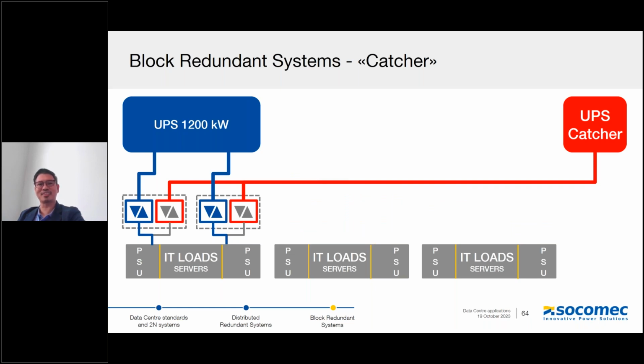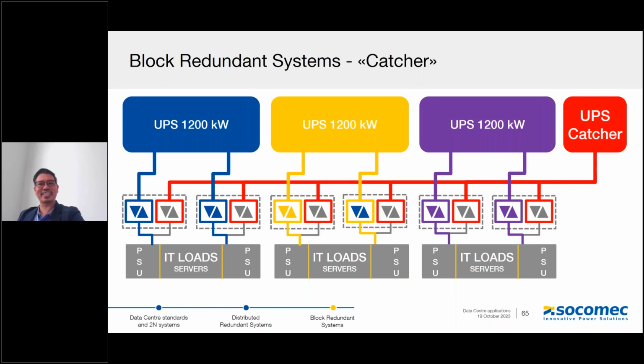You have your source B as your UPS catcher, but also your source A as your main UPS. However, the catcher won't be optimized if it is only a catcher of one system. So the catcher can be a catcher of multiple systems - that's where all your savings will go. You'll have less UPSs, meaning less UPS, less batteries as well.